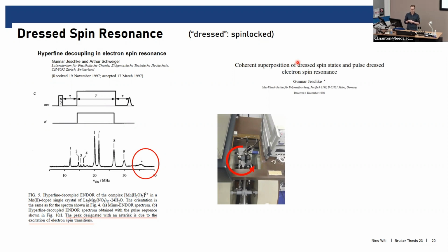And the problem is if the RF matches the nutation frequency of this spin lock, you're actually inducing a transition, and the transition moment of these transitions is due to the electron spin. So it's just 1,000 times more likely than for RF. So even if you have like sine of 1 degree, it still gives you enough that you can actually see it. So you can just take your Endor resonator and actually turn it 90 degrees.